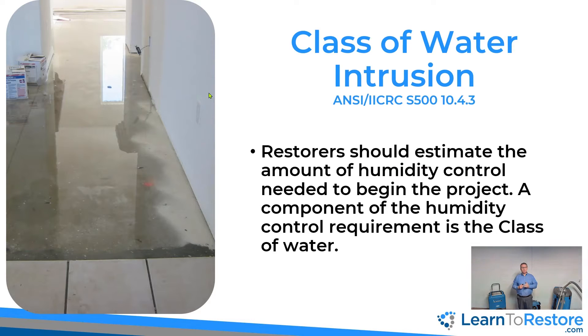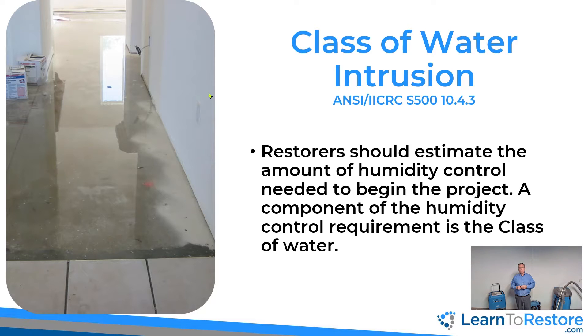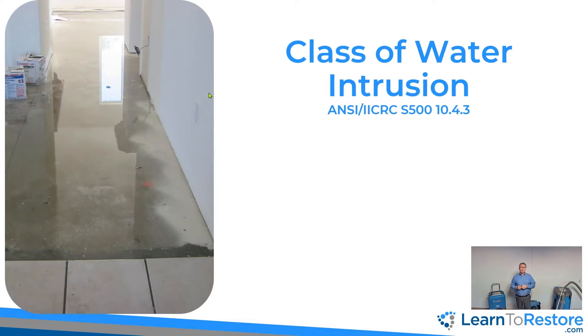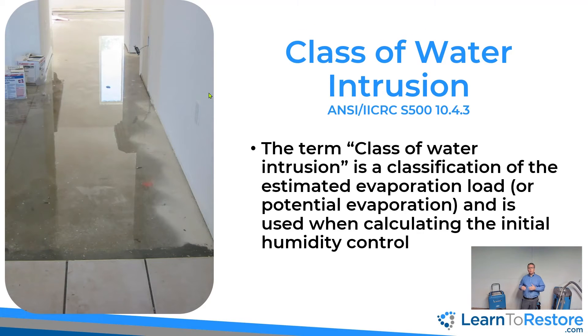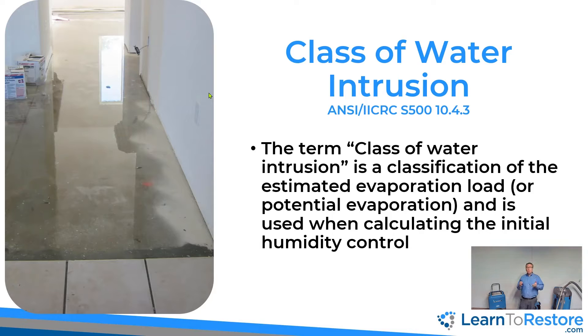The S500 tells us that as restorers, we should estimate the amount of humidity control needed at the beginning of a project. This is largely determined by the class of water. The term class of water has to do with the potential rate of evaporation, or what we call the evaporation load — in other words, how much water vapor is loading up into the air based on the types of materials that are wet and how wet they are; how much water is going to come up into the air that needs to be ventilated to the outside or dehumidified.